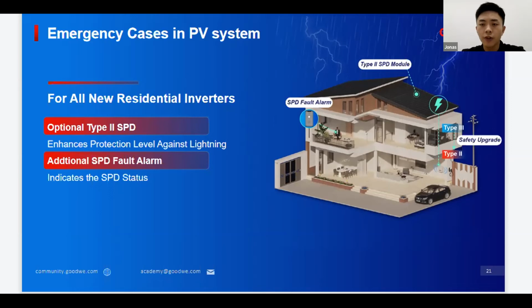What we could do this year is increase the SPD level of our residential family. Before, if you check the old data sheet of all our residential inverters, we only had type 3 regarding the SPD. If you look at the old data sheet of our residential inverters, like our XS, DNS series, and the 3-phase SDT G2 series, it always has only SPD3. SPD3 was always the standard for our residential inverters.